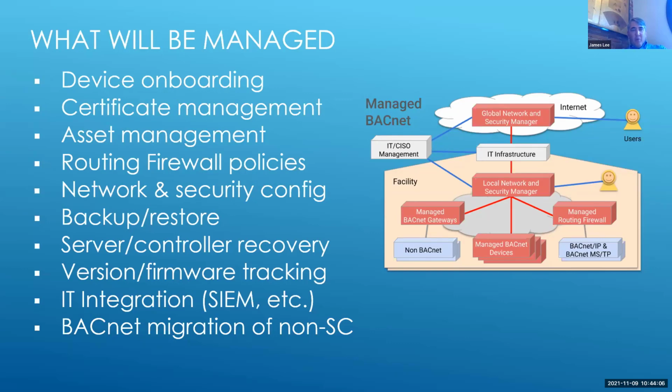Asset management. One of the things that we laugh about in the industry, but people don't know where the controllers are. They don't necessarily know where the devices are. So having a much better map of what you actually have to keep it secure is paramount in what we're working on here. How do I control what goes between those legacy networks and the secure networks? Well, I need to have routing firewall policies. And so that's an area that Managed BACnet takes care of.